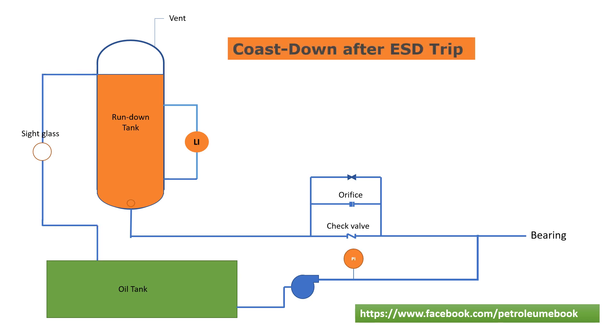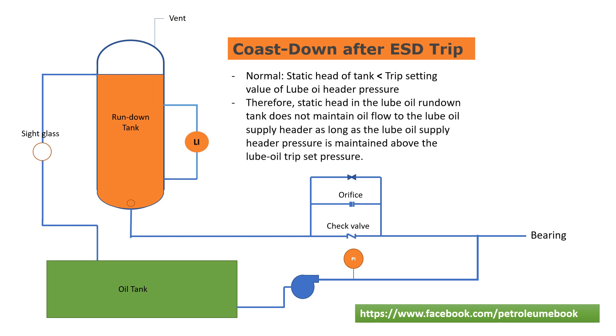Coast-down after emergency shutdown trip: by virtue of the system design, the maximum static head from the run-down tank is lower than the lube oil trip-set pressure. Therefore, the static head in the lube oil run-down tank does not maintain oil flow to the lube oil supply header as long as the lube oil supply header pressure is maintained above the lube oil trip-set pressure.